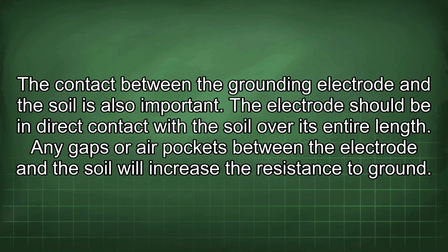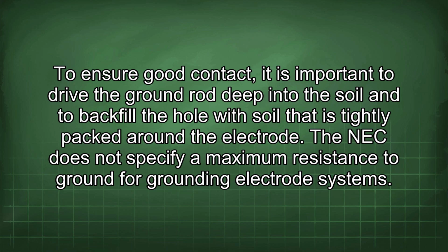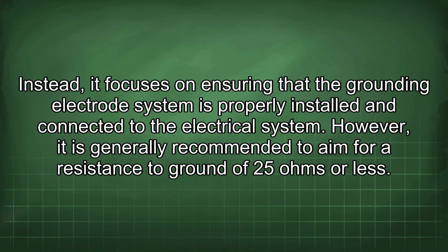Any gaps or air pockets between the electrode and the soil will increase the resistance to ground. To ensure good contact, it is important to drive the ground rod deep into the soil and to backfill the hole with soil that is tightly packed around the electrode. The NEC does not specify a maximum resistance to ground for grounding electrode systems. Instead, it focuses on ensuring that the grounding electrode system is properly installed and connected to the electrical system. However, it is generally recommended to aim for a resistance to ground of 25 ohms or less.